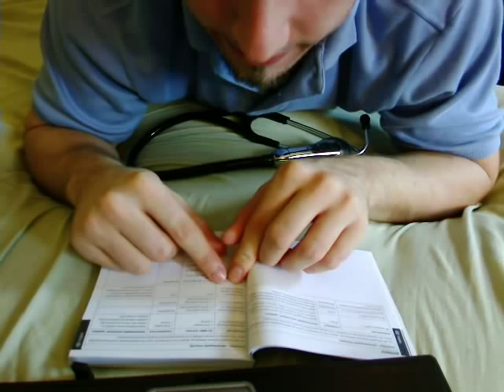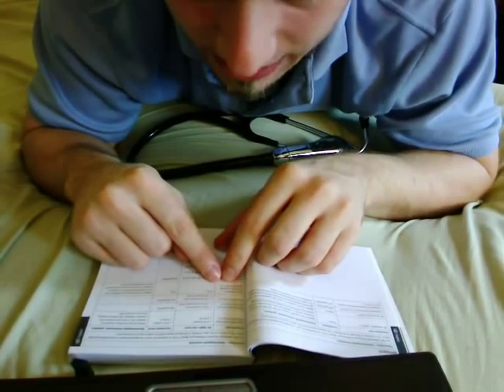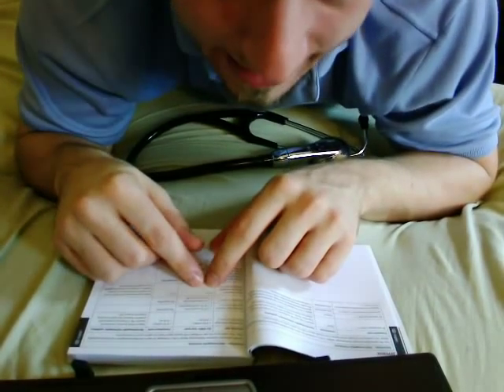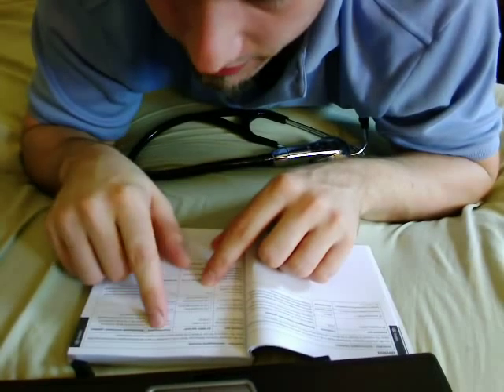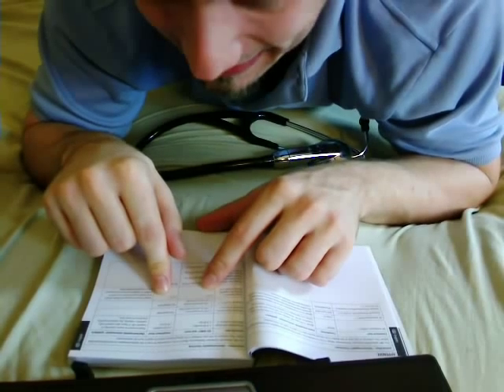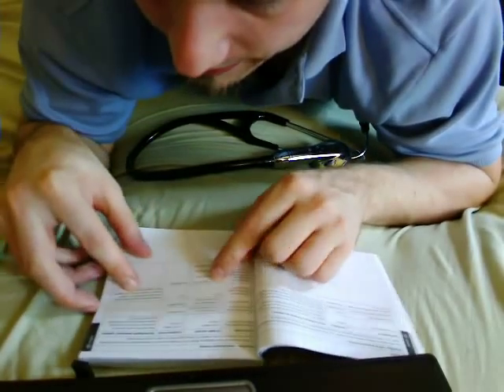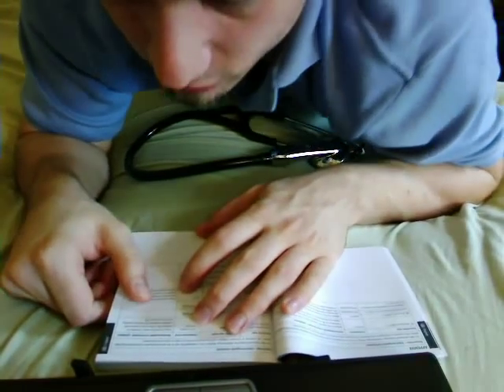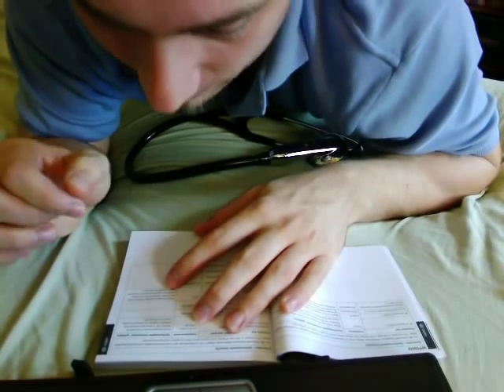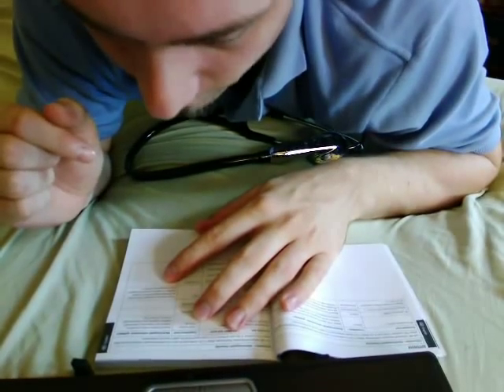Next immunity test: power frequency 50/60 Hz magnetic field, IEC 61000-4-8. The IEC 60601 test level is 3 A/m, and the compliance level is also 3 A/m — so these two are equal. The guidance for this electromagnetic environment states that power frequency magnetic fields should be at levels characteristic of a typical location in a typical commercial or hospital environment.